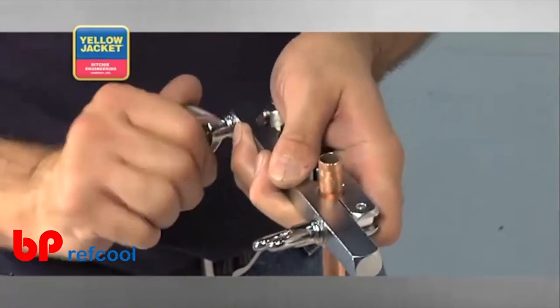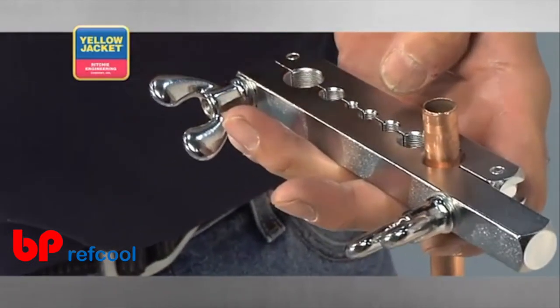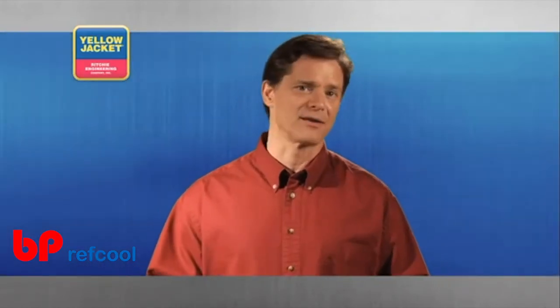Then tighten the bar starting with the butterfly nut closest to the tube. Tighten the second nut. Tightening the butterfly nuts for a swage is a little more critical due to the amount of force required to forge a swage.